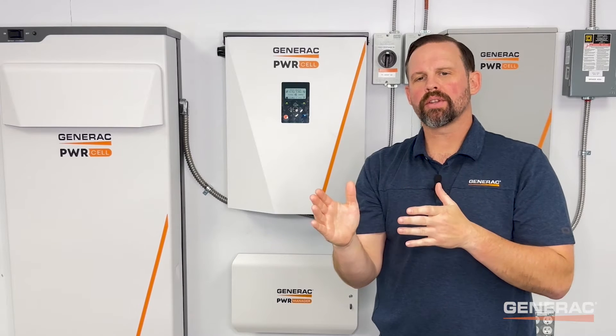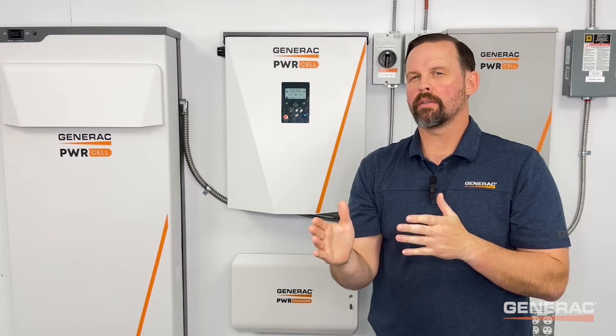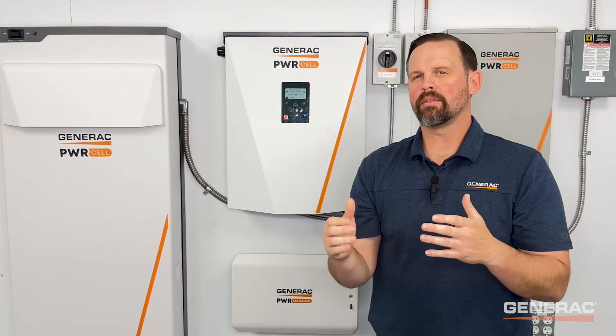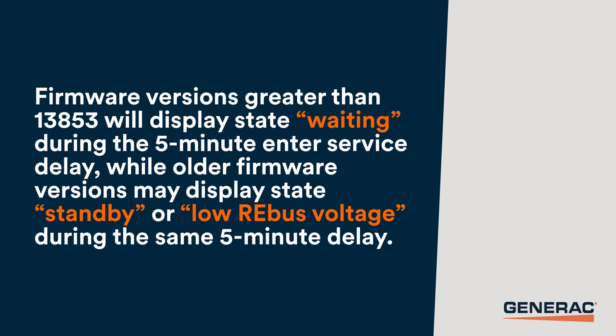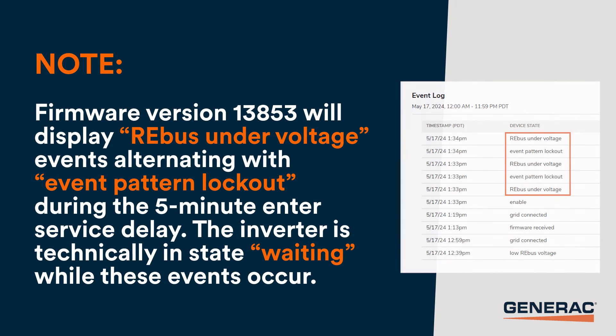New inverter firmware will enforce the enter service delay of 5 minutes upon commissioning the inverter for the first time and any time the inverter loses its grid connection thereafter. Firmware versions greater than 13.8.5.3 will display state waiting during the 5-minute enter service delay, while older firmware versions may display state standby or low rebus voltage during the same 5-minute delay. Firmware version 13.8.5.3 will display rebus under voltage events alternating with event pattern lockout during the 5-minute enter service delay. The inverter is technically in a waiting state while these events occur.